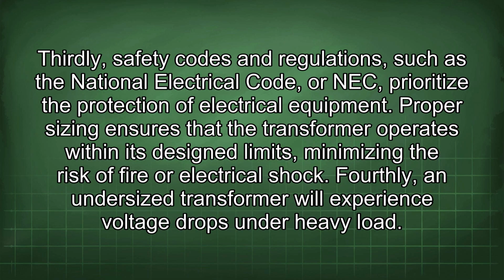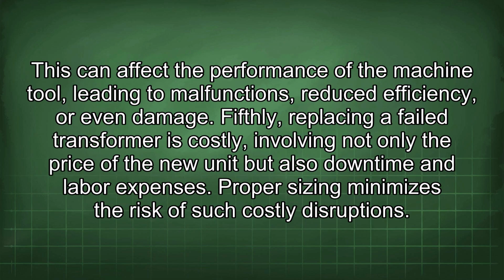Thirdly, safety codes and regulations such as the National Electrical Code, or NEC, prioritize the protection of electrical equipment. Proper sizing ensures that the transformer operates within its design limits, minimizing the risk of fire or electrical shock. Fourthly, an undersized transformer will experience voltage drops under heavy load. This can affect the performance of the machine tool, leading to malfunctions, reduced efficiency, or even damage.